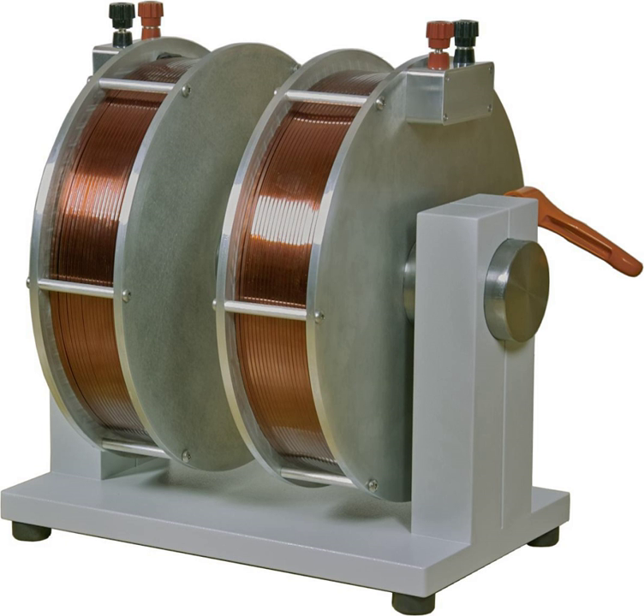If an ordinary switch is used to control the winding current, this can cause sparks at the terminals of the switch. This doesn't occur when the magnet is switched on, because the limited supply voltage causes the current through the magnet and the field energy to increase slowly, but when it is switched off, the energy in the magnetic field is suddenly returned to the circuit, causing a large voltage spike and an arc across the switch contacts, which can damage them.